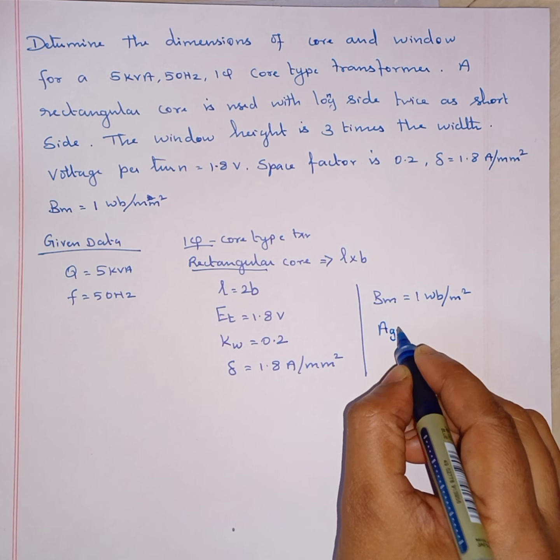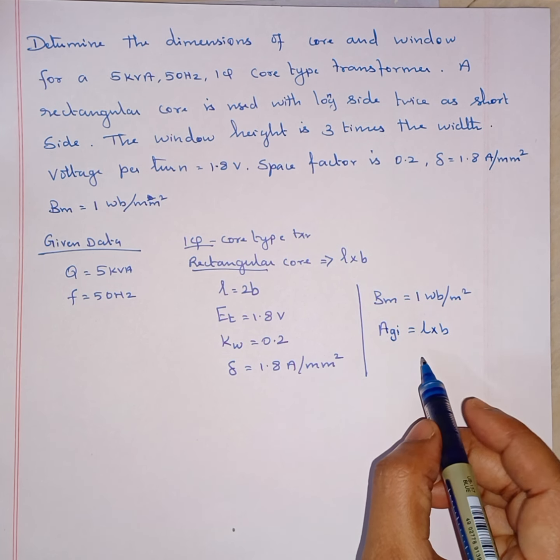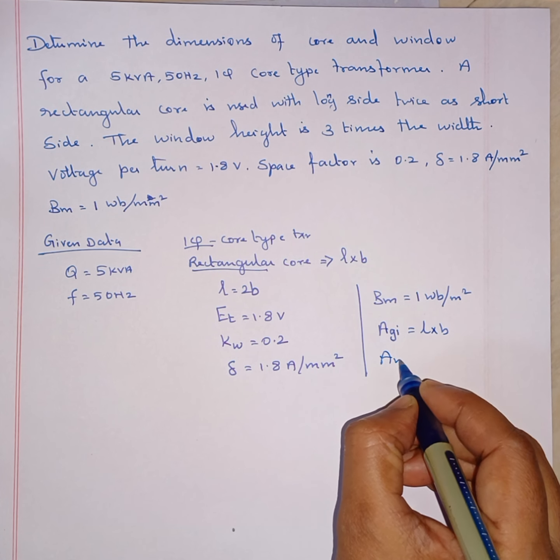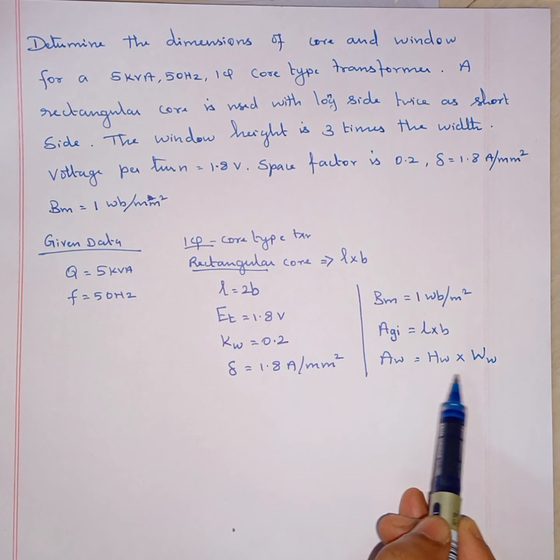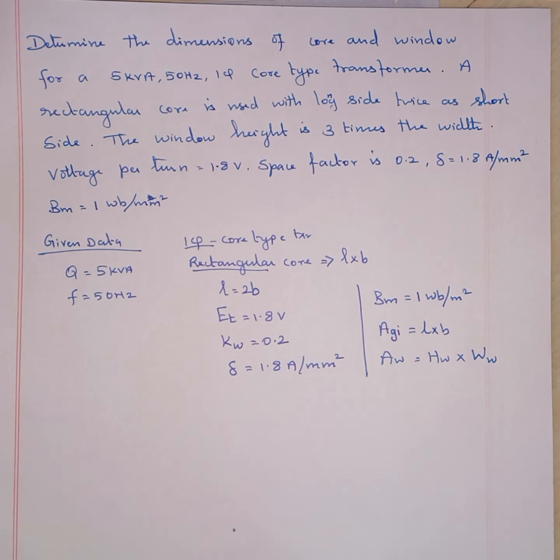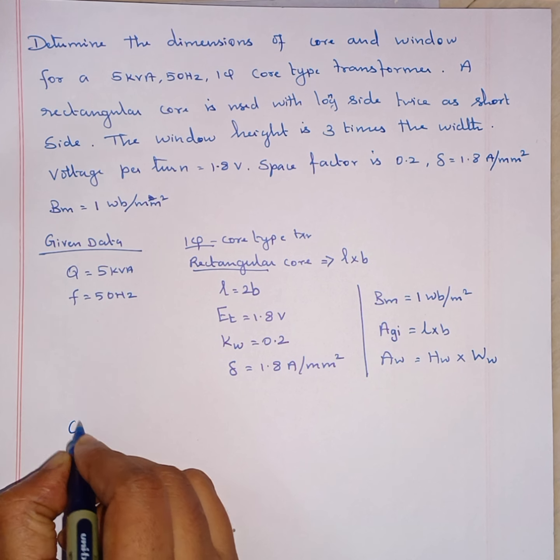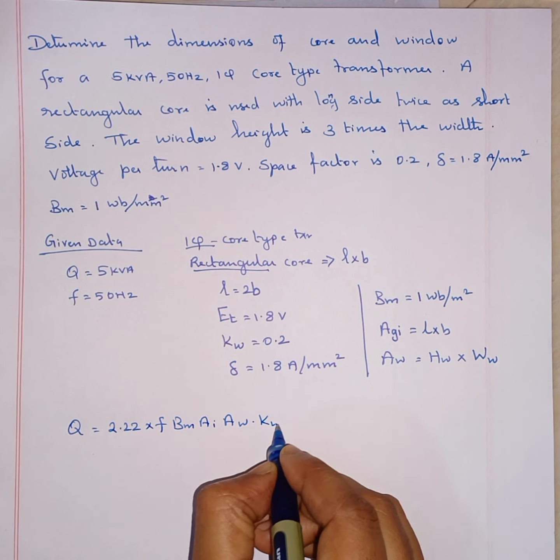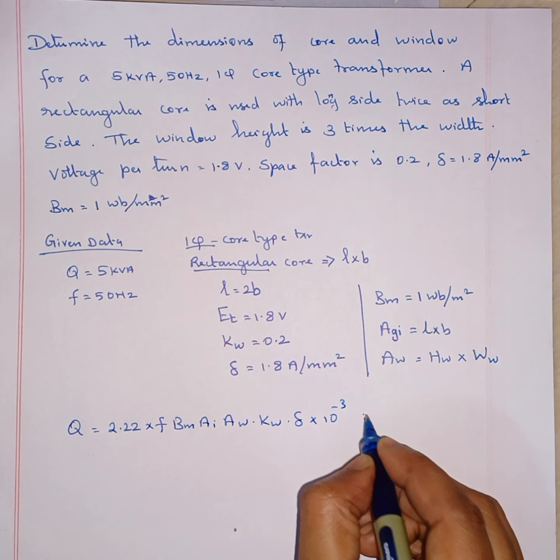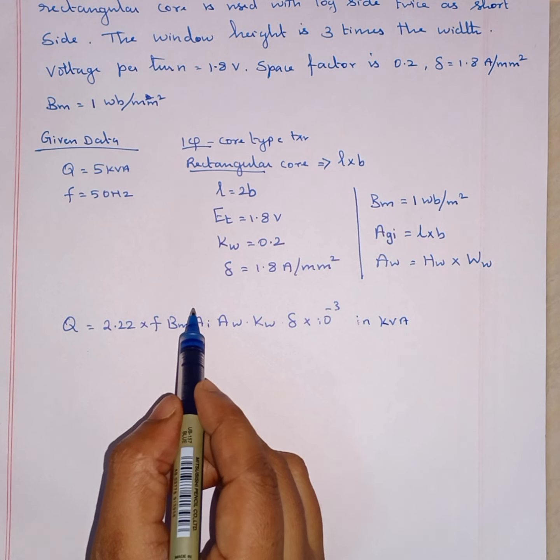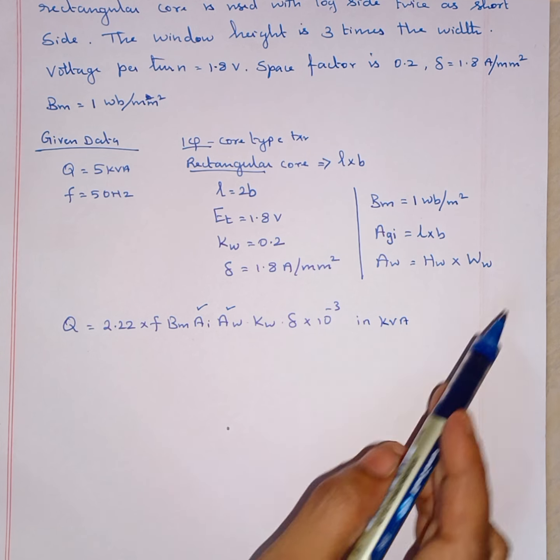Our aim is to find out dimensions of the core — which is first the area of the core. The gross iron area AGI is equal to L into B, so we have to find out L and B. Then area of the window: area of the window is equal to height of the window into width of the window. These are the dimensions: L, B, height of the window and width of the window. These type of problems use only a few formulas. First one: Q is equal to 2.22 F BM AI AW KW delta into 10 power minus 3. This is to represent Q substituted in kVA. Our aim is to find out AI and AW, from which we can find all dimensions.